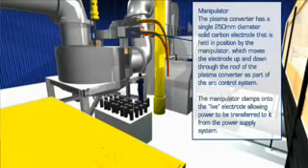The manipulator moves the electrode up and down through the roof of the plasma converter as part of the arc control system. It clamps onto the live electrode, allowing power to be transferred to it from the power supply system.